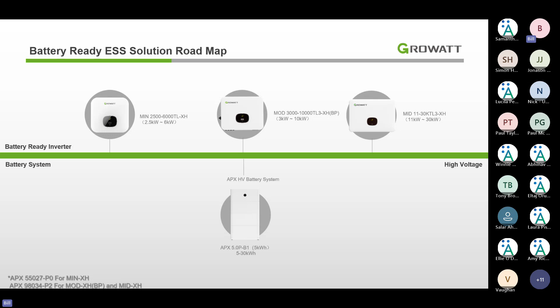The good thing for this system is that all the inverters are compatible with one high voltage battery, which is called APX. Yeah, with our APX high voltage battery system, you can scale storage from 5 kilowatt hour up to 30 kilowatt hour, making it ideal for a household with growing energy demand. So the difference would be the single phase system will use the single phase BMS, which is the APX battery. It comes with the P0 BMS. But for the three phase, the MOD and MID, they both work with the P2 BMS on top. We can go through more details later.